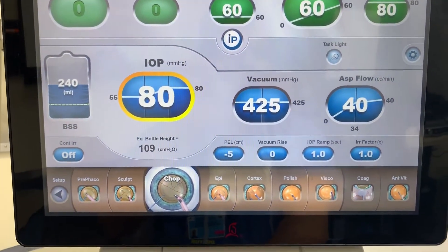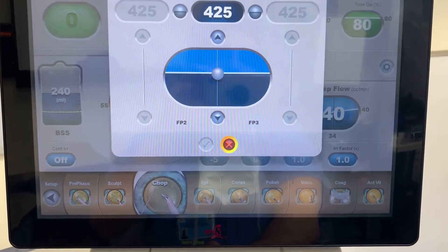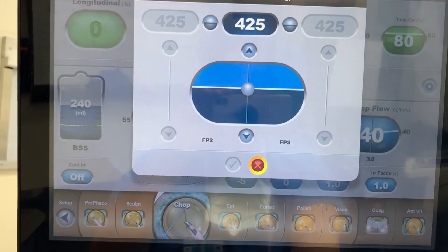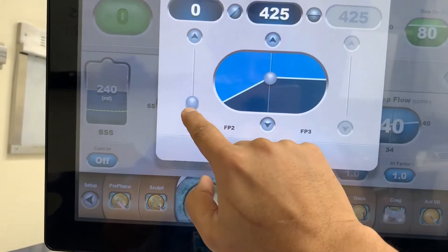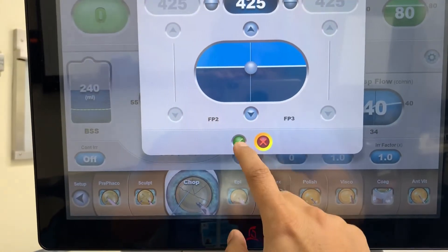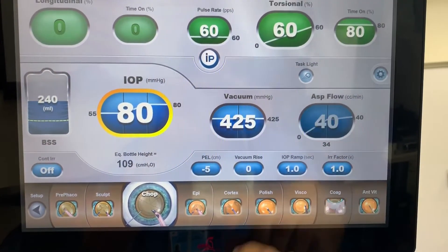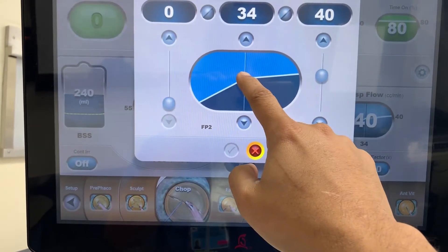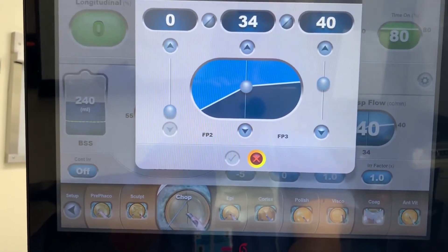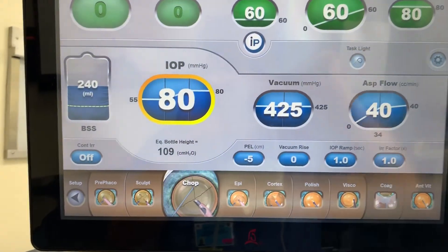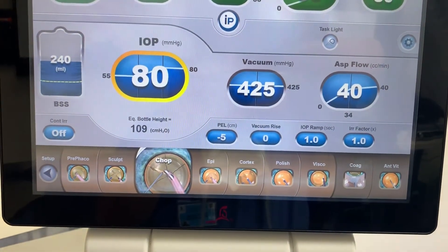When we go to chop mode, things change significantly. We have a lot more vacuum — 425 — giving us a lot more holding power to embed the probe into the nucleus. We want high vacuum right from foot position 2 to embed the FACO probe. For aspiration flow, we ramp it up: once we're taking down small pieces and chopping them up, flow increases. But when initially embedding the probe, we don't need much flow. Those are very reasonable settings for chop.